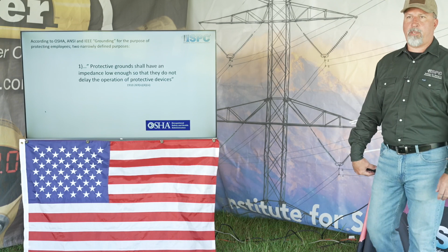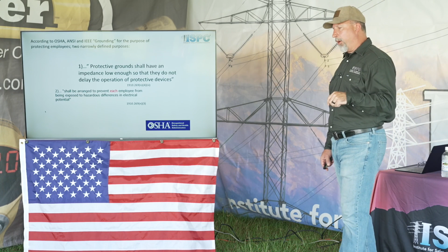So, according to OSHA and ANSI and IEEE, grounding for the purpose of protecting employees, right? A couple OSHA rules here: 269(n)(3), protective grounds shall have an impedance low enough that they do not delay the operation of protective devices, right? We just said grounding is for operating our protective relays and isolating the problem as quick as possible, right? 269(n)(3), our grounds need to be arranged to prevent each employee from being exposed to hazardous differences in potential, right?